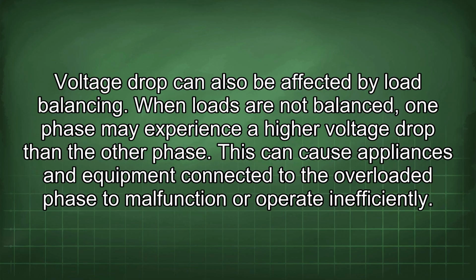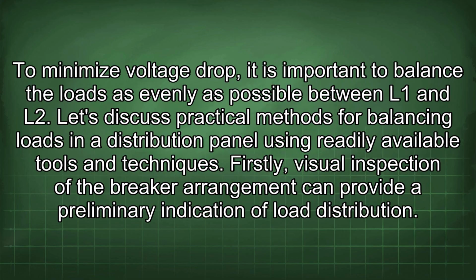Voltage drop can also be affected by load balancing. When loads are not balanced, one phase may experience a higher voltage drop than the other phase. This can cause appliances and equipment connected to the overloaded phase to malfunction or operate inefficiently. To minimize voltage drop, it is important to balance the loads as evenly as possible between L1 and L2. Let's discuss practical methods for balancing loads in the distribution panel using readily available tools and techniques.